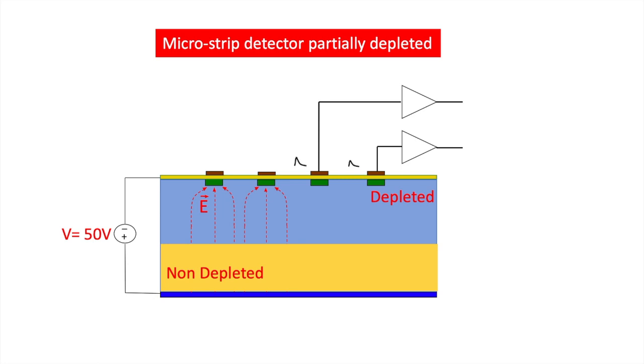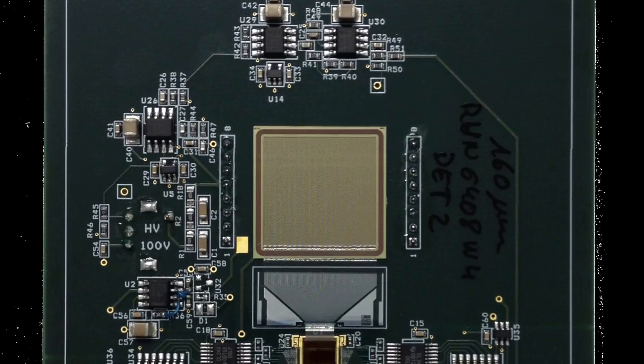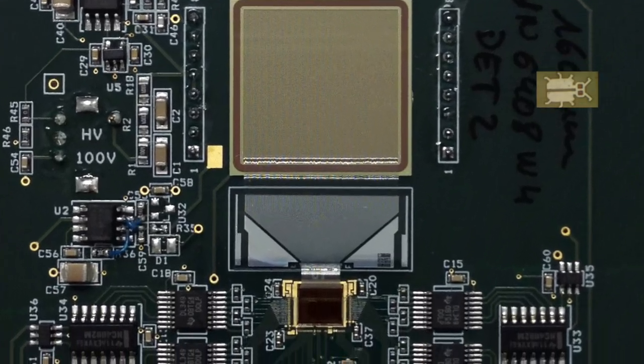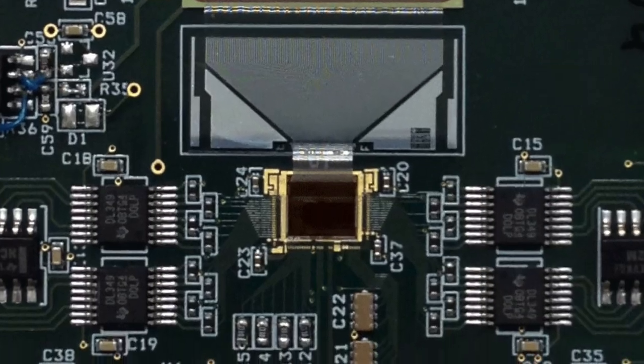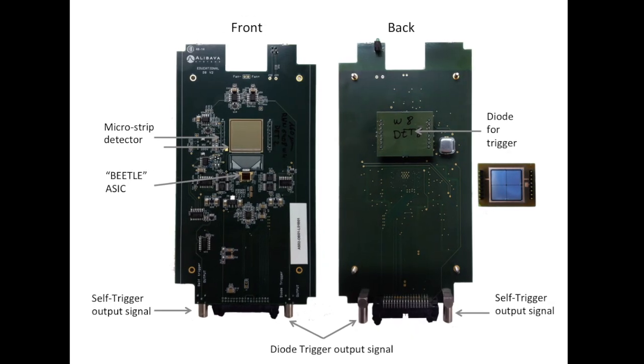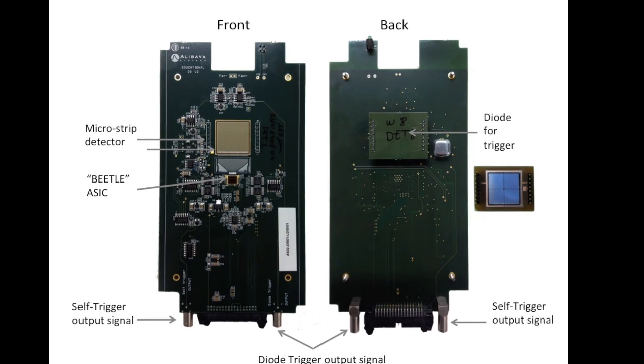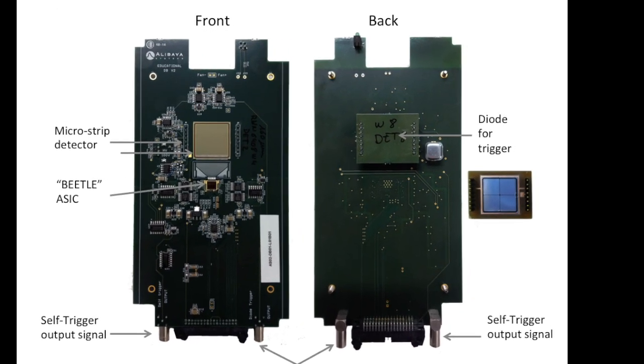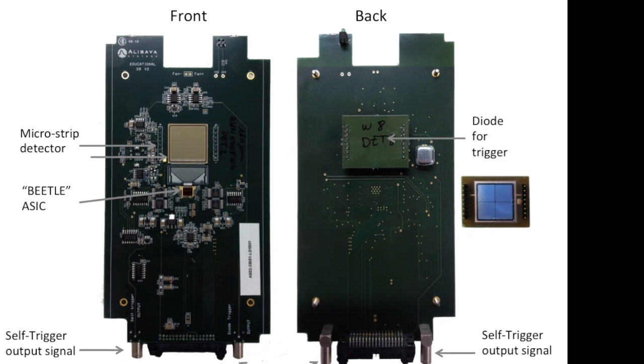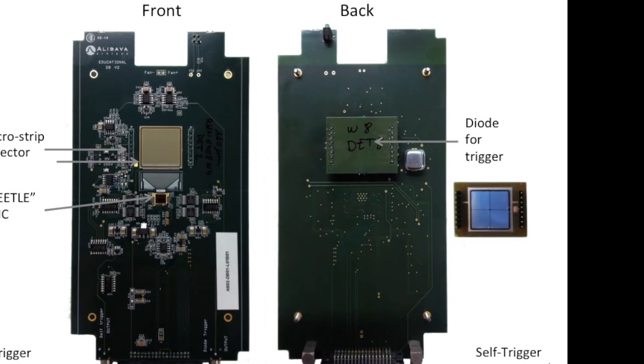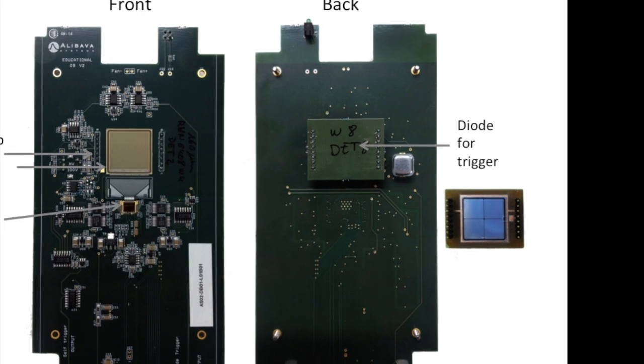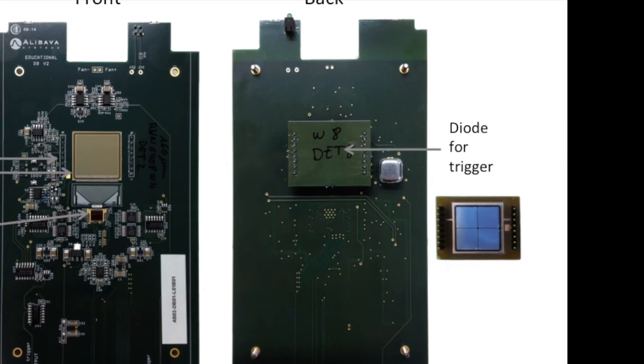The signal generated in silicon detectors is generally of small amplitude, around 24,000 electrons for a fully depleted 300 micron sensor, hence amplification and shaping stages are required for its further processing. The readout and amplification of the signal of the detector is done by the Beetle chip, developed for CERN LHC experiments. The sensor unit also generates trigger signals, which are useful to indicate the exact time at which a particle crosses the microstrip sensor. One of the possible trigger modes of the EASY system is the diode trigger mode.